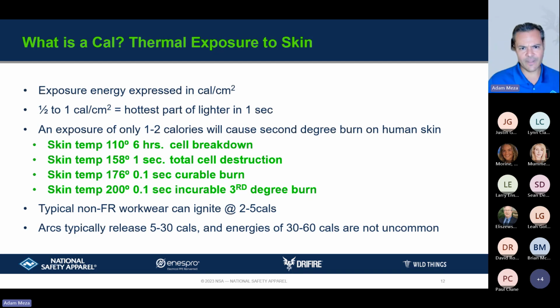There's a lot of information on that slide. The one data point I want you to remember is 200 degrees, one-tenth of a second, incurable third-degree burn. That is bad, you can't come back from that. The skin won't. And something good to remember: street clothes will ignite at 2 to 5 calories. So if you're wearing any meltables, that garment is going to melt and stick to your body.